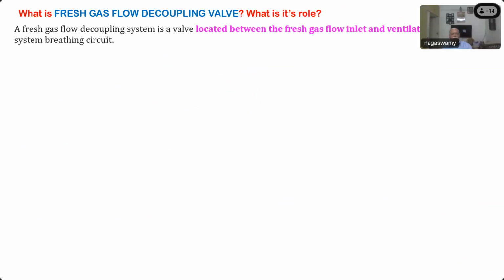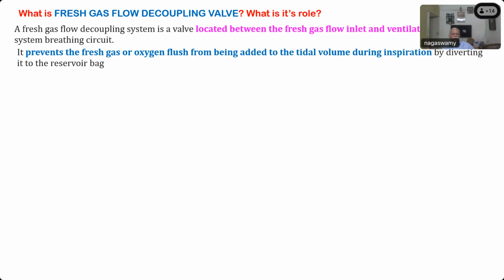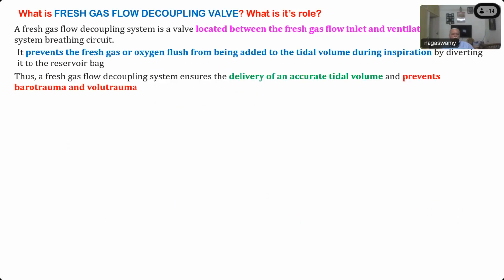It prevents the addition of fresh gas flow to the tidal volume delivered by the ventilator, sir. Very good. So only the set tidal volume from the machine will be delivered, and fresh gas flow will have no effect. Fresh gas flow decoupling is a valve located between the fresh gas flow inlet and the ventilator in a circle system breathing circuit. It prevents fresh gas or oxygen flush from being added to the tidal volume during inspiration by diverting it to the reservoir bag. Thus, it ensures delivery of the accurate tidal volume and prevents barotrauma and volutrauma. So these are all the roles played by this.